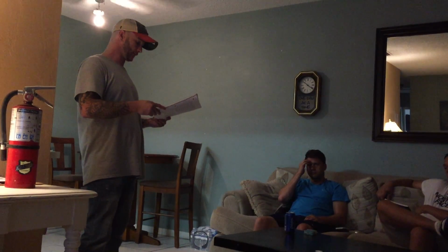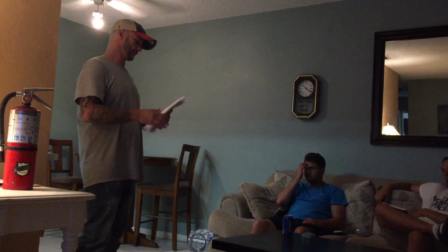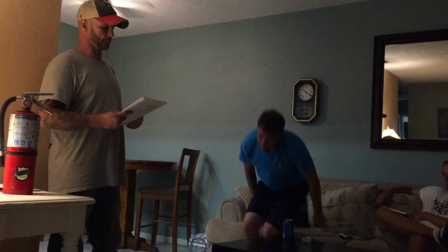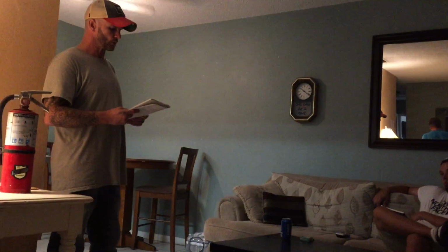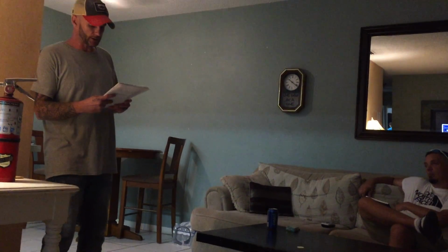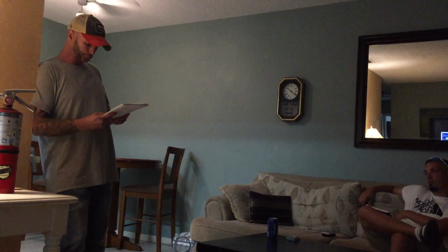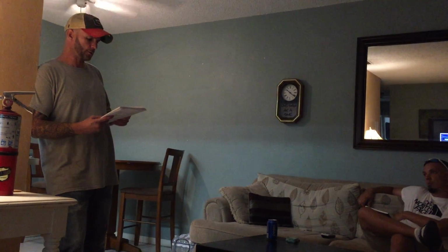Carbon dioxide fire extinguishers, also known as CO2. CO2 is a gas that is 1.5 times heavier than air. When it's discharged on a fire, it forms a dense cloud that displaces the air surrounding the fuel, which interrupts the combustion process by reducing the amount of oxygen that can reach the fuel. Carbon dioxide is rated for Class B and Class C fires as well.